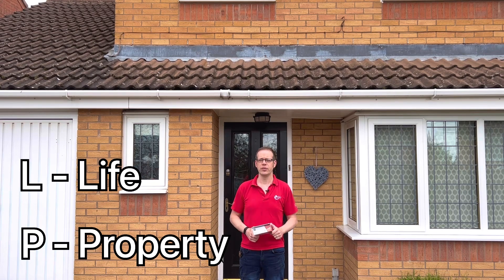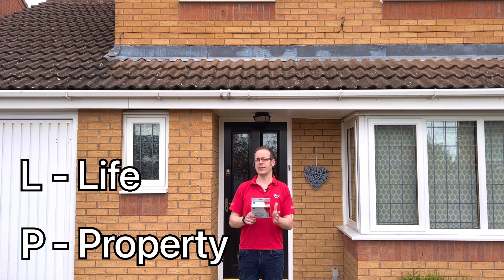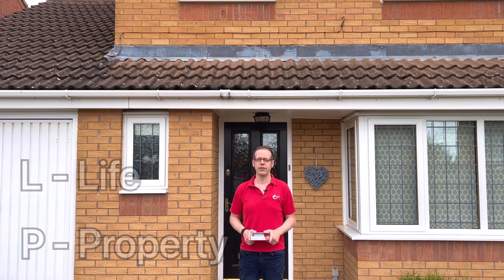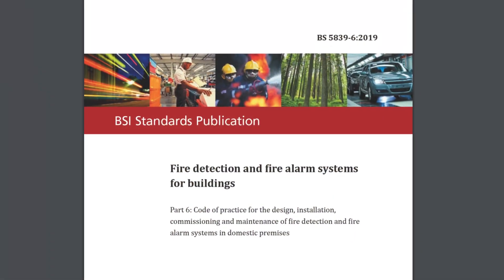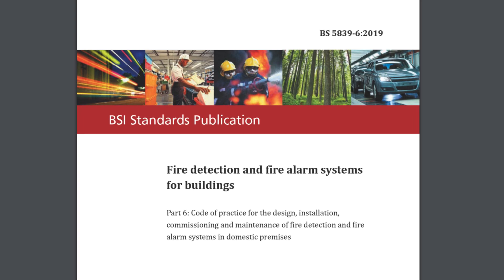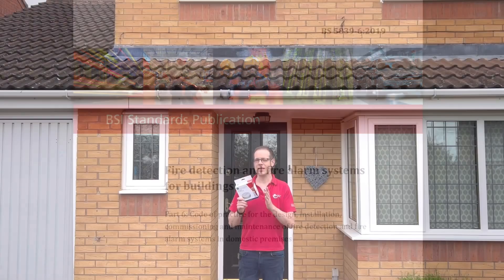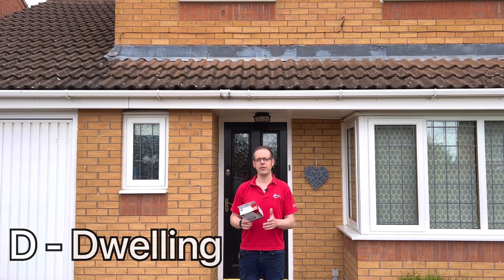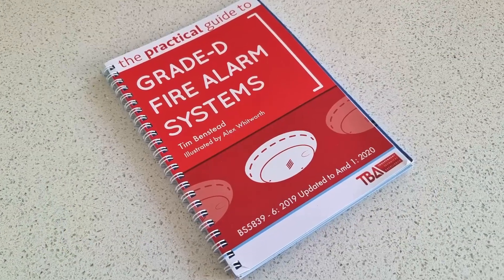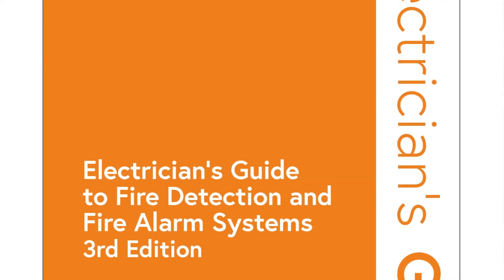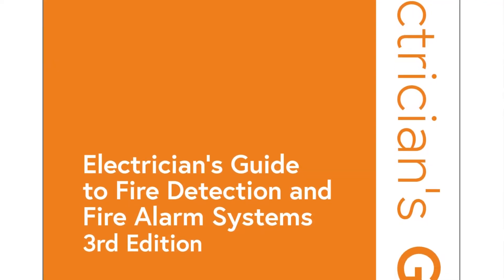These are the identifying letters used in BS5839-1, but this information doesn't relate so much to dwellings — for that you need to refer to BS5839-6. This standard adds an additional identifying letter, D for dwelling, and these are the categories we'll be looking at in this video. Much of the information we'll be referring to can be found in the Practical Guide to Grade D Fire Alarm Systems available on docstore.co.uk and the Electrician's Guide to Fire Detection and Fire Alarm Systems published by the IET.